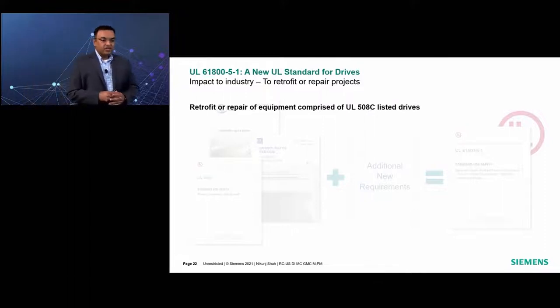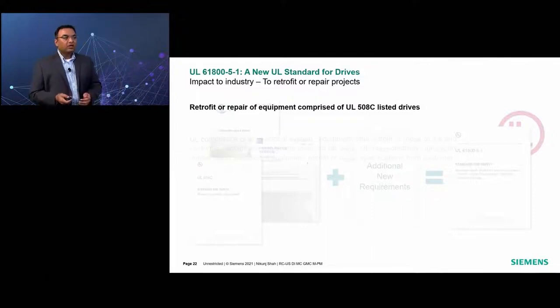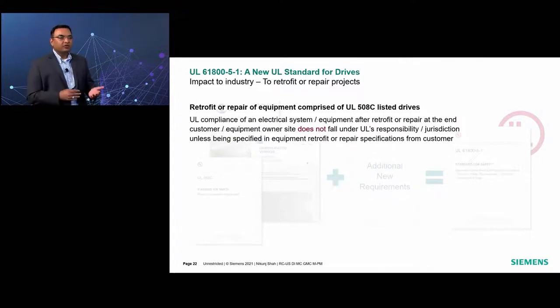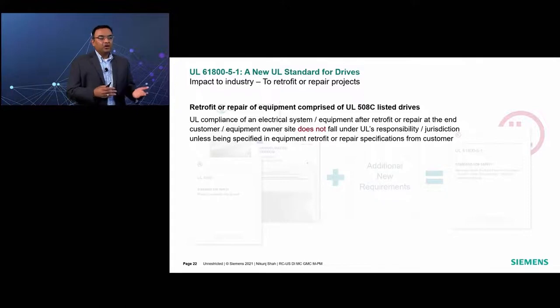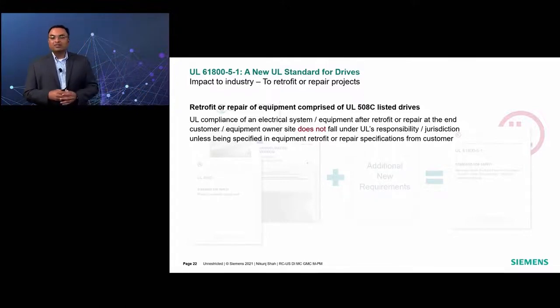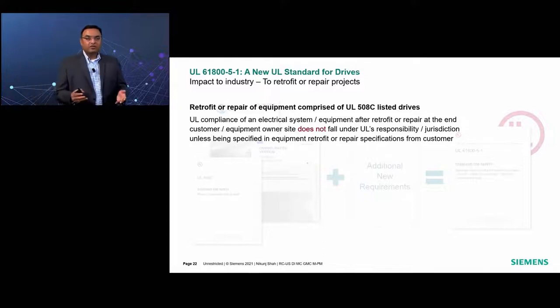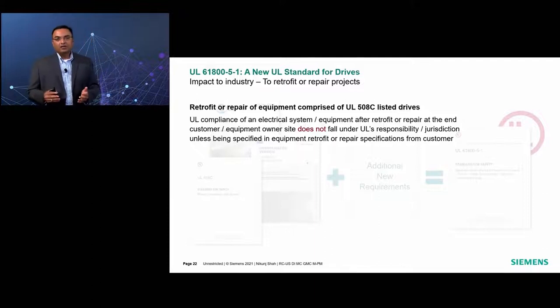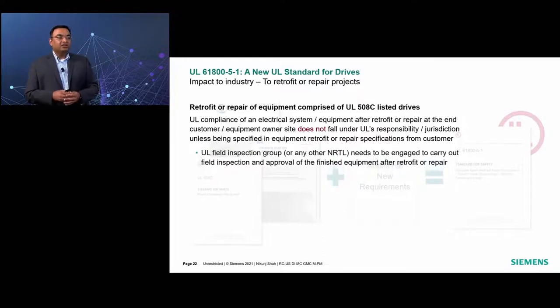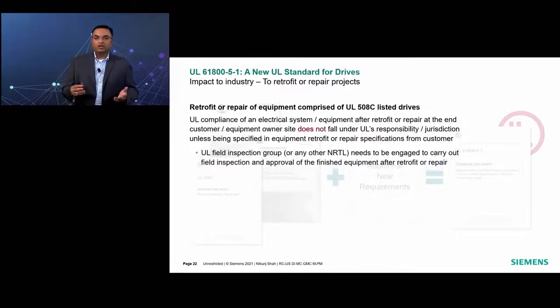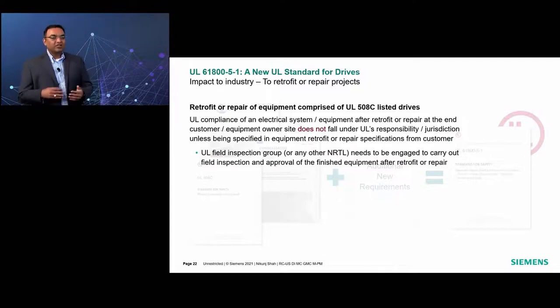Now let us see what this change means to a retrofit job or a repair of equipment which comprises an old UL 508C listed drive. Typically, the UL compliance of the electrical system or equipment after the retrofit or repair at the end customer or equipment owner side does not fall under UL's responsibility or jurisdiction unless it is clearly specified in the equipment retrofit or repair specifications from the manufacturer. If it is specified in the manufacturer's customer specifications, then the UL field inspection group or any other NRTL, which is a nationally recognized testing lab, needs to be engaged to carry out the field inspection and approval of the finished equipment after the retrofit or repair job is done.